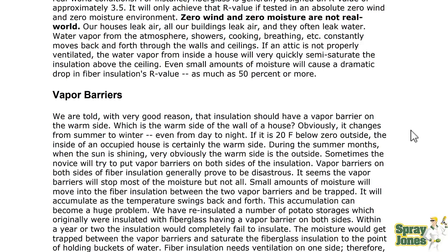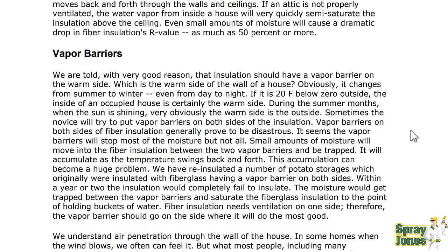We're told that insulation should have a vapor barrier on the warm side of the wall, which obviously changes from summer to winter, even day or night. If it's 20 degrees Fahrenheit below zero outside with the sun shining, the warm side is clearly the outside. Sometimes the novice will try to put vapor barriers on both sides of the insulation. Vapor barriers on both sides of fiber generally prove to be disastrous — the vapor barriers will stop most of the moisture but not all, since we're punching them full of holes, and this accumulation can become a huge problem.